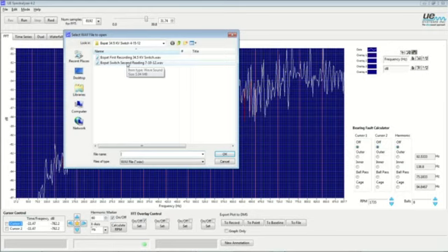And severity is a tricky but important thing to determine, because in a lot of the mechanical applications using ultrasound, we rely upon decibel level to help us gauge severity. And the thing I can't stress enough to our customers and to anybody using the Ultraprobe in electrical applications, the decibel level has absolutely nothing to do with the severity of the fault we are talking about.